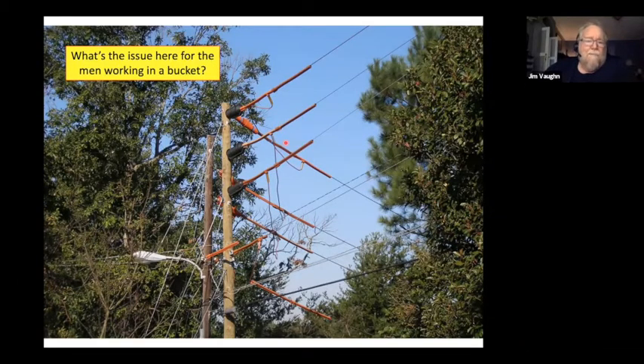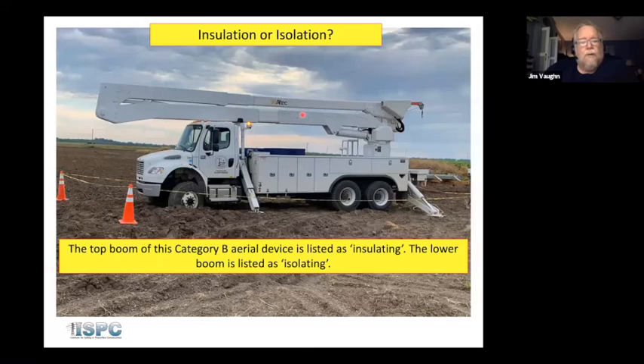So when we talk about MAD and we talk about cover up, we stand back and we look at the work environment and we identify these risks. And if we need to, we get in there with a saw and we trim trees out and we create working clearance so that we can get work in there safely. And by the way, it's kind of like moving out on a ladder on transmission. If you've got your hands on this conductor out here, then you have a MAD distance between yourself and those trees that you need to consider. And that's how you determine how far back you need to trim those trees.